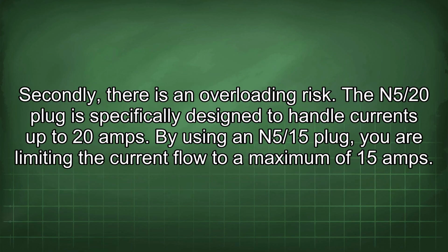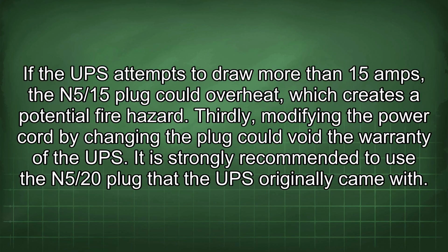Secondly, there is an overloading risk. The N5/20 plug is specifically designed to handle currents up to 20 amps. By using an N5/15 plug, you are limiting the current flow to a maximum of 15 amps. If the UPS attempts to draw more than 15 amps, the N5/15 plug could overheat, which creates a potential fire hazard. Thirdly, modifying the power cord by changing the plug could void the warranty of the UPS. It is strongly recommended to use the N5/20 plug that the UPS originally came with.